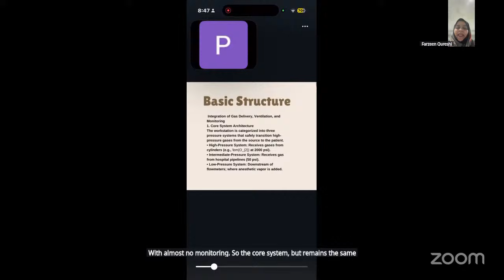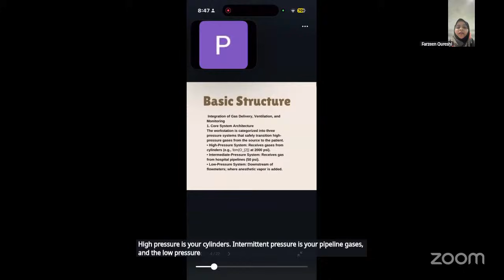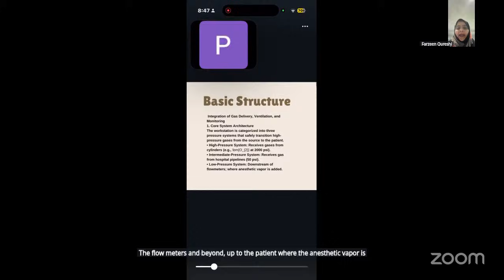We have the same transition from high pressure to the patient. High pressure is your cylinders, intermediate pressure is your pipeline gases, and the low pressure becomes the flow meters and beyond up to the patient, where the anesthetic vapor is also added. So the basic structure remains very much the same.